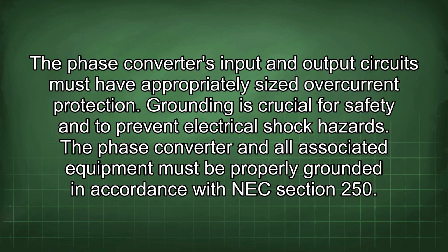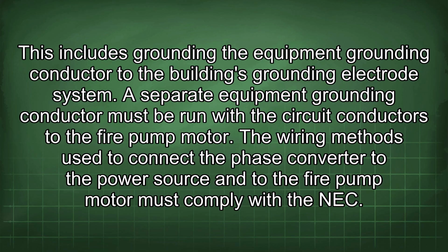Grounding is crucial for safety and to prevent electrical shock hazards. The phase converter and all associated equipment must be properly grounded in accordance with NEC Section 250. This includes grounding the equipment grounding conductor to the building's grounding electrode system. A separate equipment grounding conductor must be run with the circuit conductors to the fire pump motor.